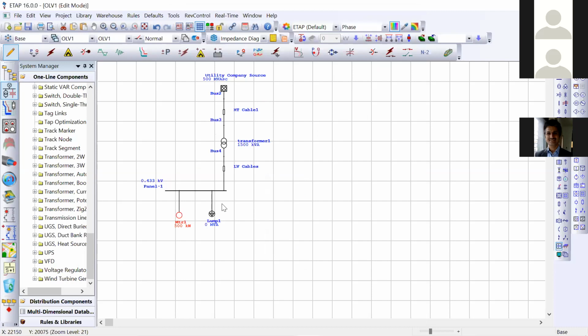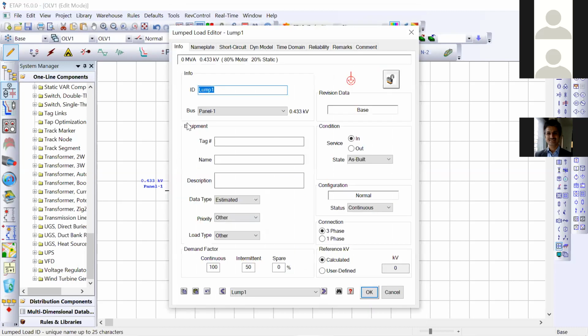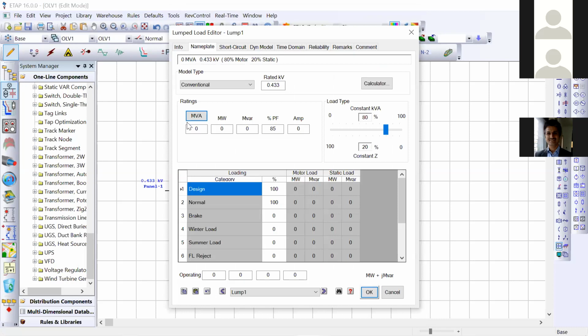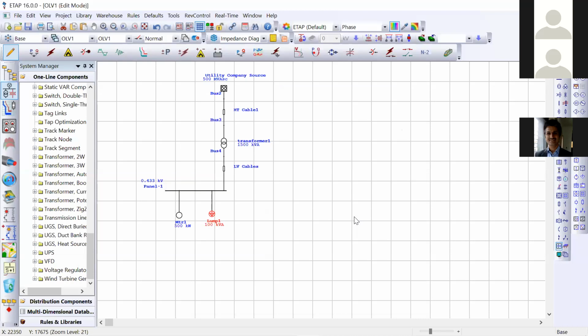and lump load I am taking 100 kVA. So with this, all my elements are now in place in my single line diagram. Now we will go for checking load flow first and then short circuit analysis.